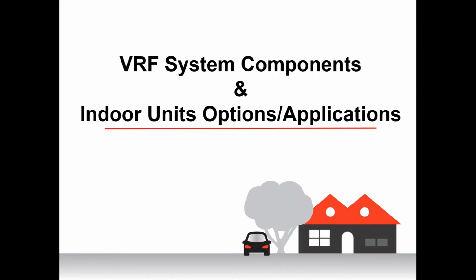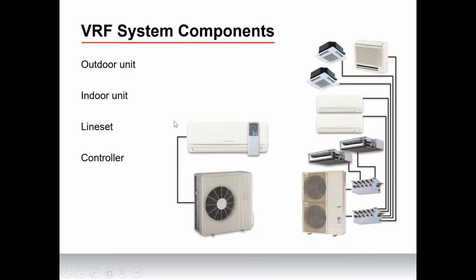So what makes up a VRF heat pump system, and what are some different indoor unit options and applications? Now that we know the difference between a traditional heat pump and a cold climate heat pump, what kind of equipment makes up that system? A basic single zone VRF air source heat pump, which we can see right here in the middle of the screen, has an outdoor unit and an indoor unit.